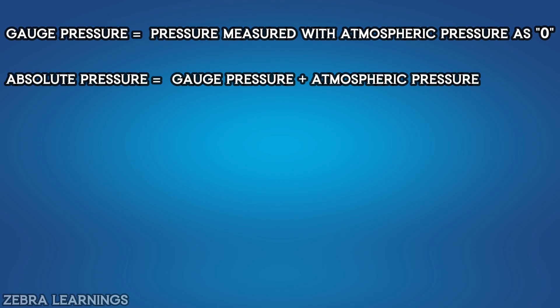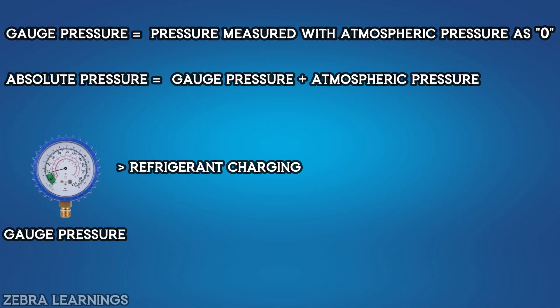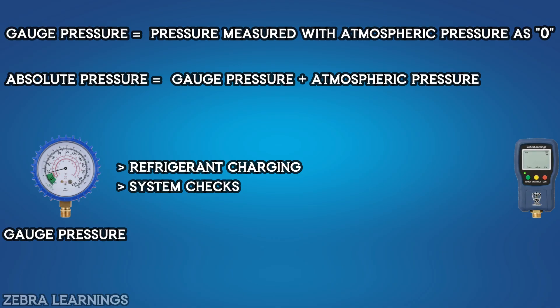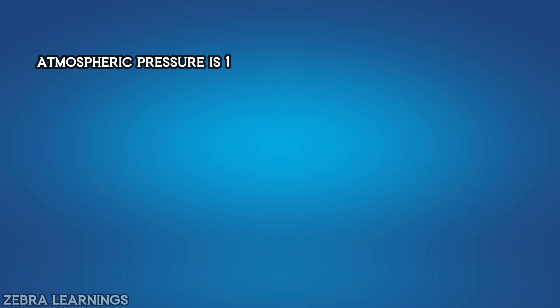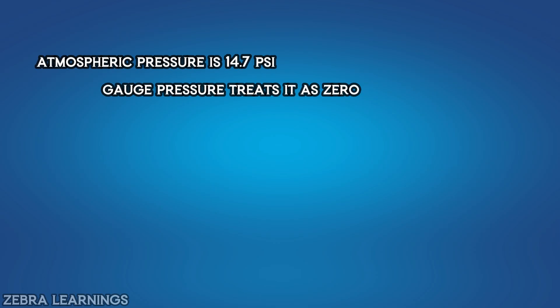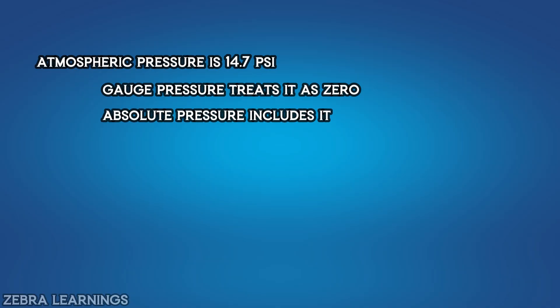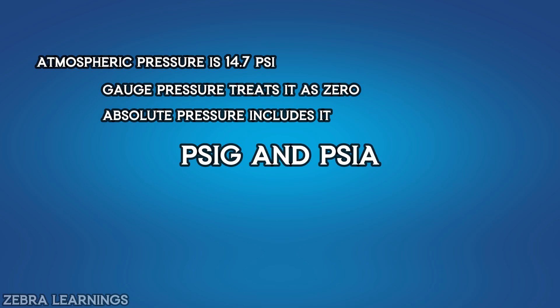In HVAC, we always use gauge pressure for refrigerant charging and system checks, and absolute pressure when measuring deep vacuum using a micron gauge. So remember: atmospheric pressure is 14.7 PSI. Gauge pressure treats it as 0, while absolute pressure includes it. That's the key difference between PSIG and PSIA.